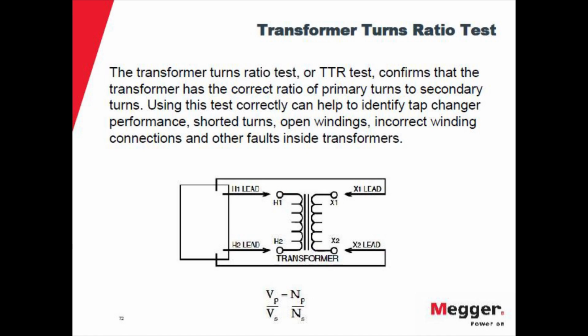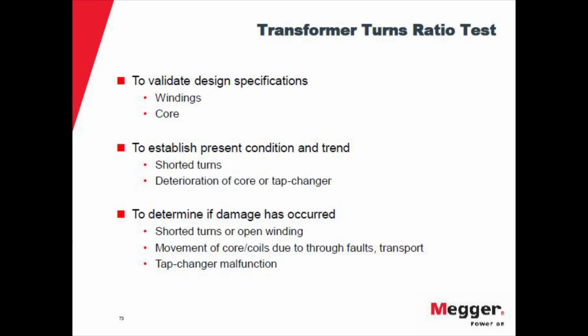So transformer turns ratio: you apply a voltage on one side of the transformer, you measure the voltage on the other side of the transformer, and that relates the number of turns on the primary side to the number of turns on the secondary side. That is a very basic test that you perform on a transformer. And you validate the design specifications with this test. And this is when you are accepting the transformer in a maintenance environment.